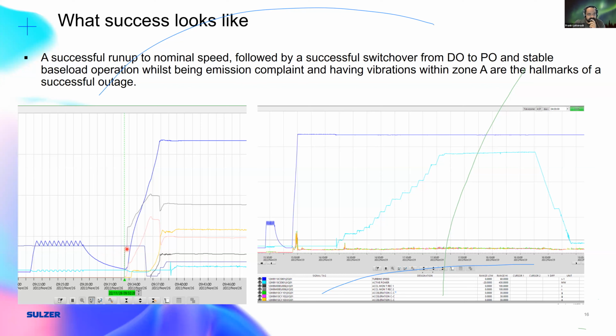Now, if you are successful, you should see an increase in temperature, pretty steep, and then it should drop when your bleed valves close, and then remain more or less constant. The reason is that different parts of the turbine heat up differently, and you want them to be as uniform as possible to reduce your vibrations on the system. Once that is complete, the synchronization process will occur here. This is the light blue line.